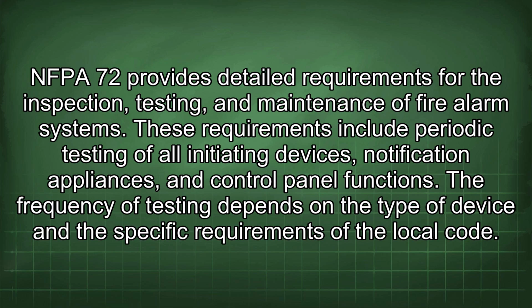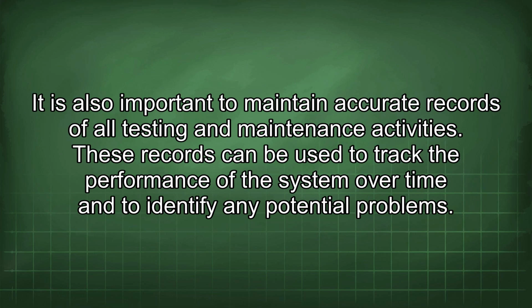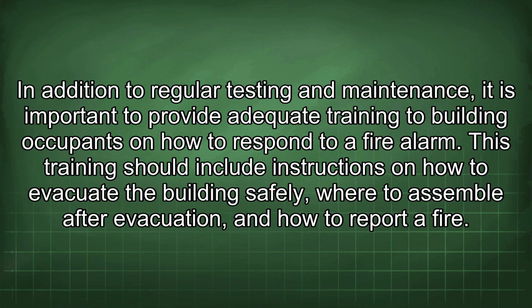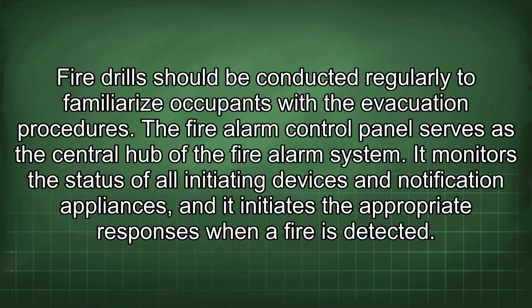The frequency of testing depends on the type of device and the specific requirements of the local code. It is also important to maintain accurate records of all testing and maintenance activities. These records can be used to track the performance of the system over time and to identify any potential problems. In addition to regular testing and maintenance, it is important to provide adequate training to building occupants on how to respond to a fire alarm. This training should include instructions on how to evacuate the building safely, where to assemble after evacuation, and how to report a fire. Fire drills should be conducted regularly to familiarize occupants with the evacuation procedures.